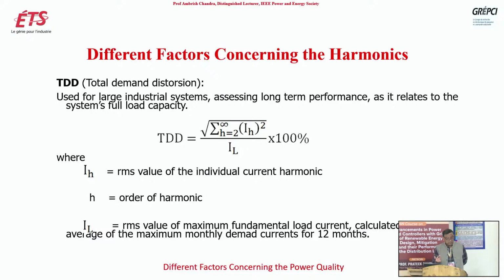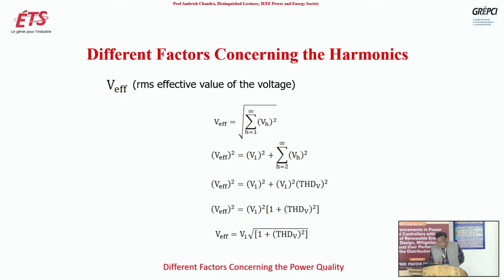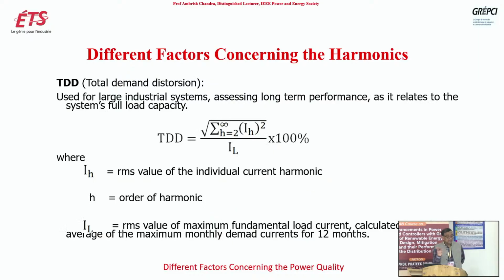For our system, THD is good enough, but TDD also has the same limits. Okay, I will come to that later. TDD also has the same limit, like we always talk about 5% as the maximum THD, but the individual harmonic current limit may be different. We will see that in the table. So this is the difference between THD and TDD.